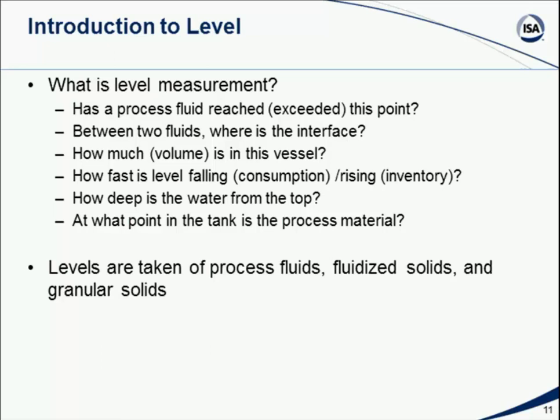Or if a tank might contain a couple of fluids, for example, in the storage of hydrocarbon refined products such as gasoline, jet fuel, and such, it's very common to have water that either seeps in or is part of the process that's resulting from the refining. And storage tanks quite often end up with a certain layer of bottoms, water and other stuff, that's underneath the hydrocarbons. So you might know where the level in the tank is, but you don't really know how much of that is actually your product and how much of that is the bottom. So sometimes we want to find the interface point between two fluids, or sometimes we're talking about the actual volume.